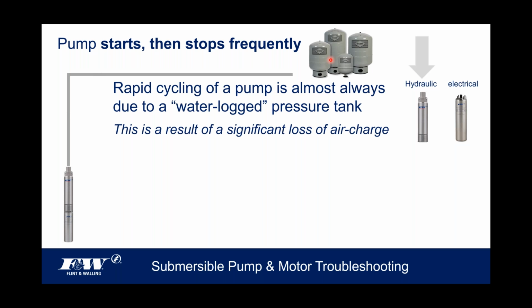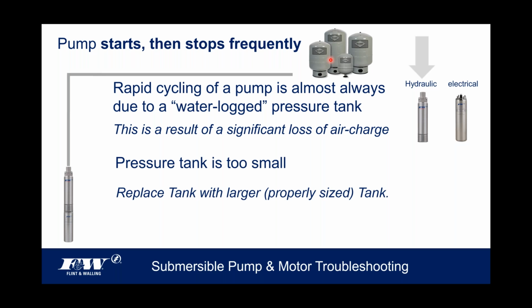There is another reason for this, and we're still on the hydraulic side. We're still talking about the tank side of this assembly, the water side of it. If the pressure tank's too small, say you've got a 19-gallon-a-minute pump and a 5-gallon pressure tank at the top, I'm just throwing this out there, so it's fictitious, I hope, to some degree. Well, how long is it going to take that pump to fill that tank? Not very long, right? So it comes on and it shuts off. Then you use that little bit of water and it comes on and it shuts off. So again, if the tank's not waterlogged, there's a chance that the tank's undersized. It just needs to be a larger pressure tank.